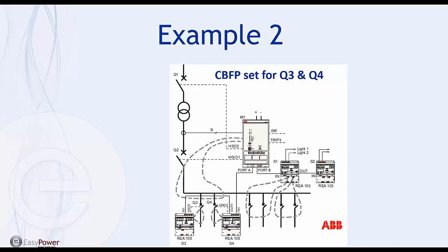So when it sees that arcing fault, it's going to trip its own dedicated high-speed output contact, and that's the only feeder that's going to be removed from the system, so you've achieved your selectivity. So let's take a look at how the dip switches are set.